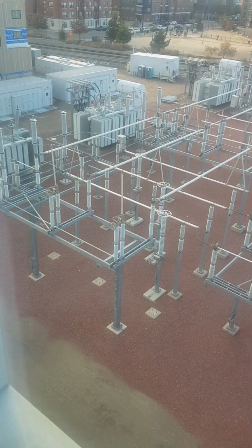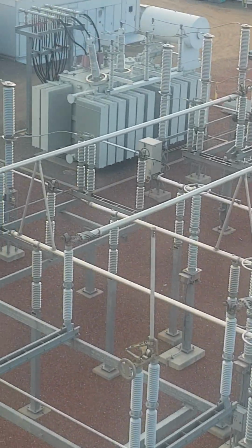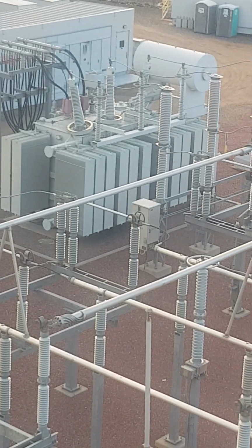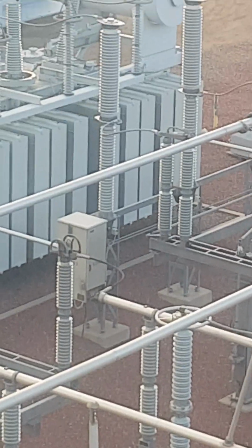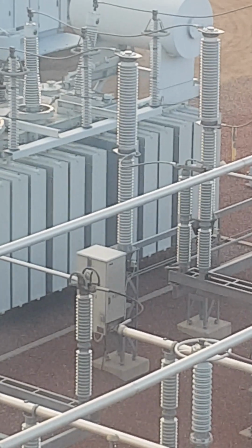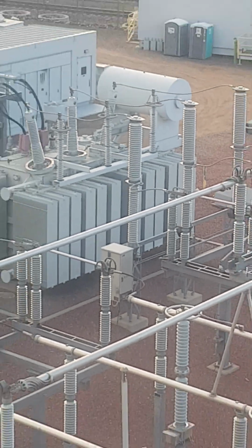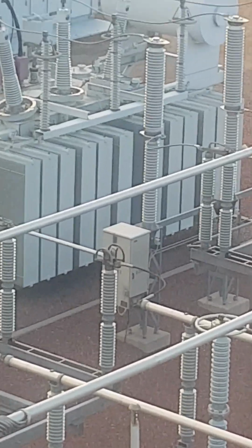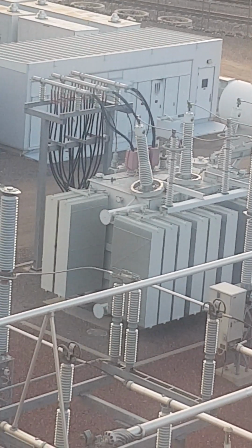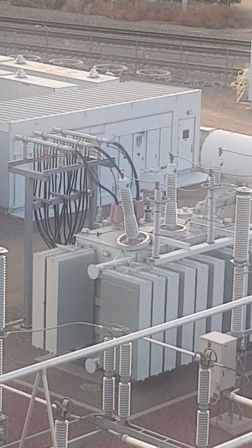And then at the end, we have my favorite part, which is the transformer that does the step down. Again, as you can see at the beginning of the transformer, there is still the CVT, the capacitive voltage transformer, to measure the voltage that enters the transformer. We have here again another surge arrestor to protect the transformer from any lightning. Then we have the high voltage bushings. And then you have the other side here, you see the low voltage bushings, and you see all these cables coming out of it. This is to feed the primary circuit of the distribution system.